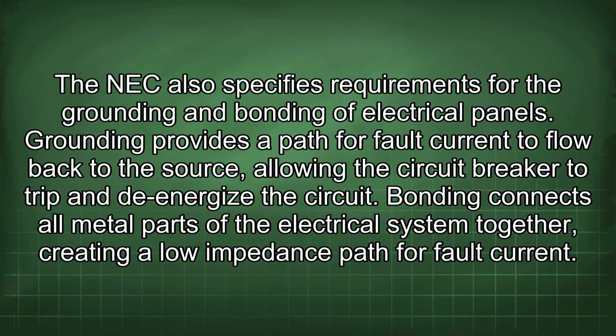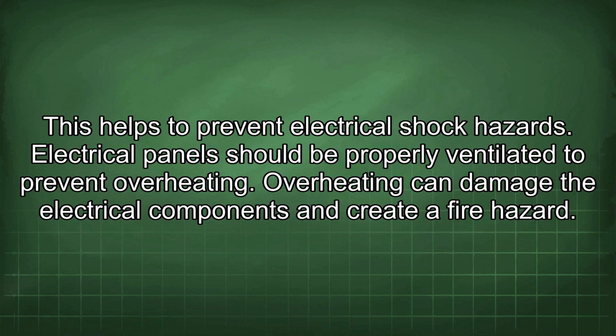The NEC also specifies requirements for the grounding and bonding of electrical panels. Grounding provides a path for fault current to flow back to the source, allowing the circuit breaker to trip and de-energize the circuit. Bonding connects all metal parts of the electrical system together, creating a low impedance path for fault current. This helps to prevent electrical shock hazards.